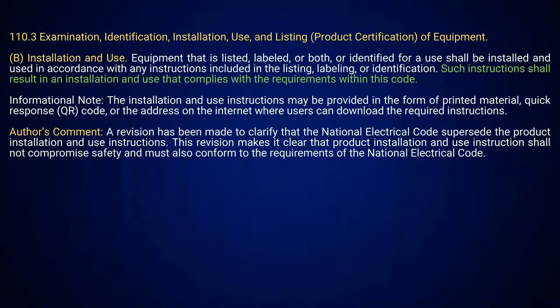If this comes to me, I can tell you right now, as the representing expert on the other side, NFPA would be brought into this, just because of this comment right here that they supersede what the product installation use instructions say. If the manufacturer says there are compatibility issues, do not put GFCI protection on, and something happens, all of a sudden who's responsible? Because you did exactly what the manufacturer told you not to do. There becomes a problem at that point, and based on what it says right here, they literally said they supersede what it says.